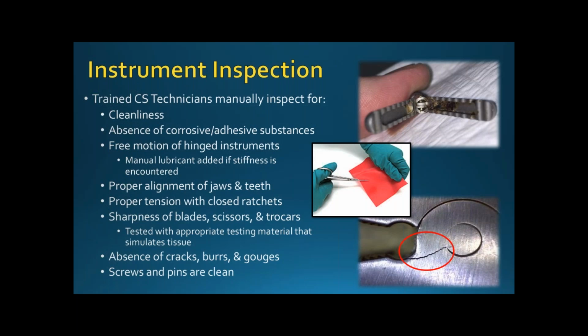After your instruments go through the washer or manual cleaning process, they'll go over to the other side, the clean side, where they go through instrument inspection. This is where the central sterile techs do manual inspection to make sure things are clean, there's no corrosion, everything works and functions right, there's no tears, the teeth line up on the equipment, and checking the sharpness of the blade. They actually have rubber band-like tensile things that mimic how tough skin and tissue are. They test all these things, and if they find anything, they set it aside to either get replaced or repaired.